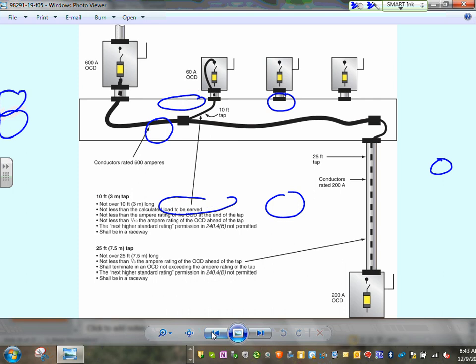This diagram is really nice because it summarizes the rules for the tap. What is a tap? When you take a bigger conductor, can you see? Here's a number 10 conductor here. This is probably a number 6 conductor, and you're tapping it from 600, let's say two sets of 500 kcmil, maybe a little bit more. So you take a bigger conductor and you tap from it a smaller conductor for 25 feet. Then you put the overcurrent protection device. Any comments, guys? Any questions?